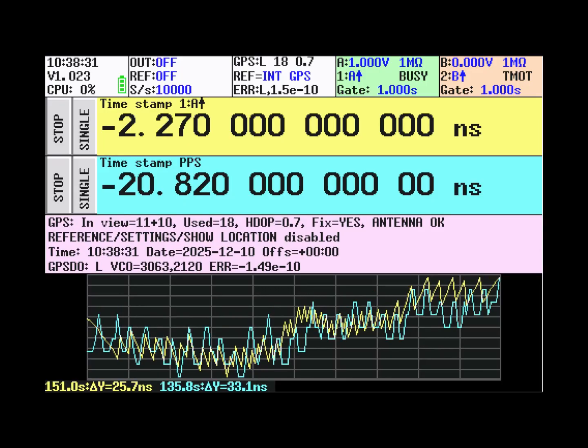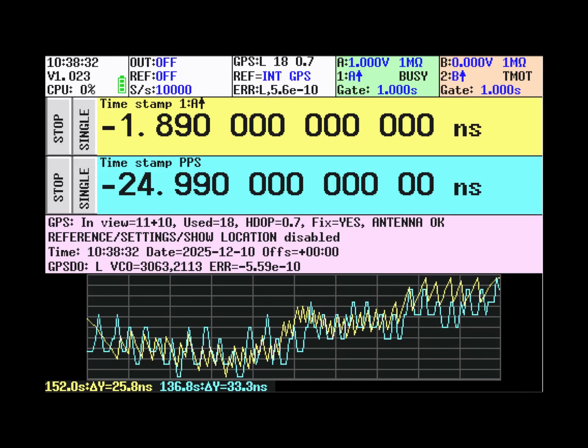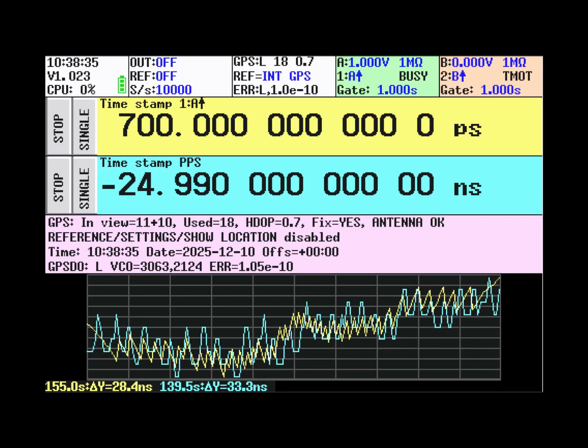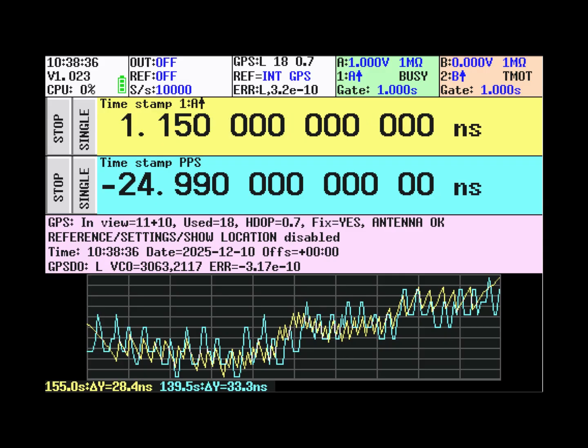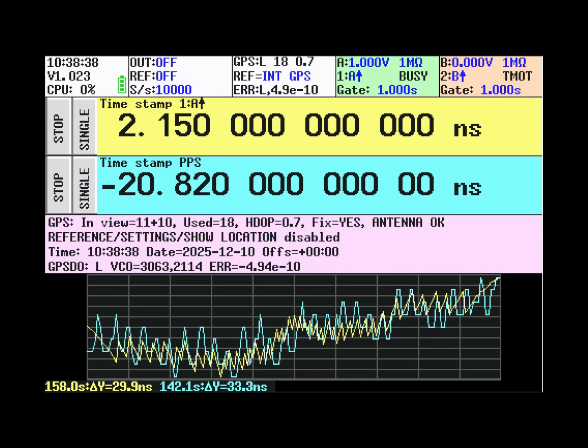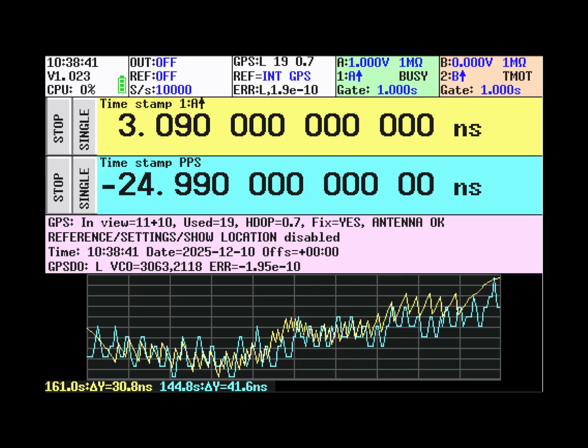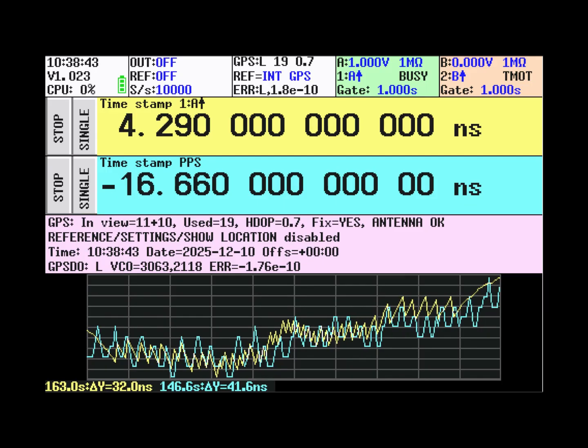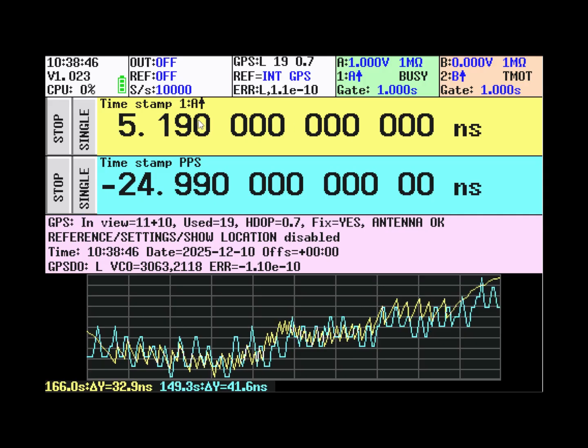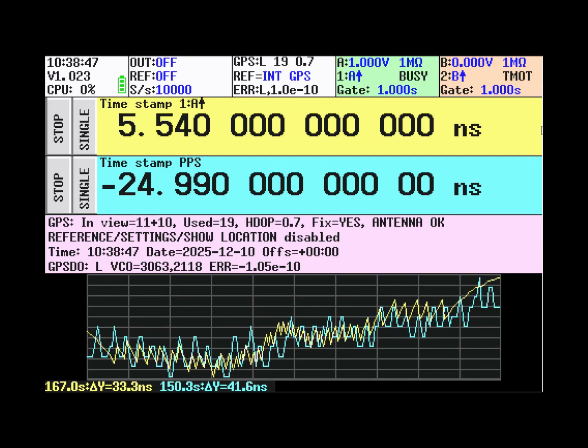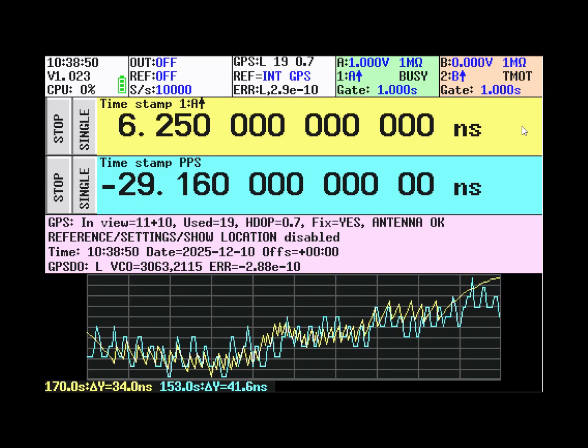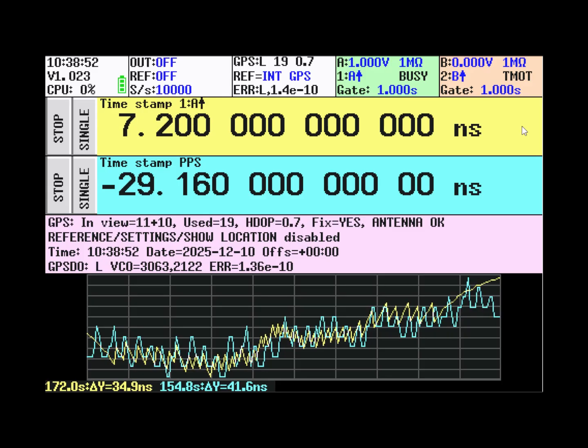After connecting the PPS output from a standalone GPS module that is locked in position, that should output a very nice one pulse per second to the A input.